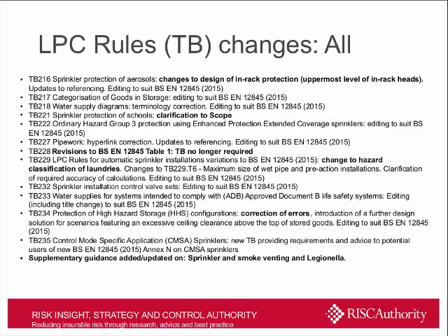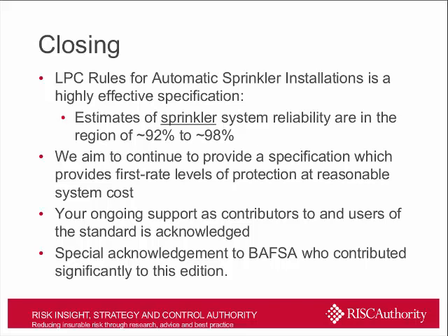As I say, these two slides really are meant to be a source of reference to you. So the slides and the webinar will be made available to you shortly after we complete. So in conclusion, the LPC Rules for automatic sprinkler installations is a highly effective specification. Estimates of sprinkler system reliability are in the region of 92%, and that figure tracks back to NFPA 13 systems. And the estimate for corresponding UK systems, which in the main will be LPC Rules systems, is approximately 98%.